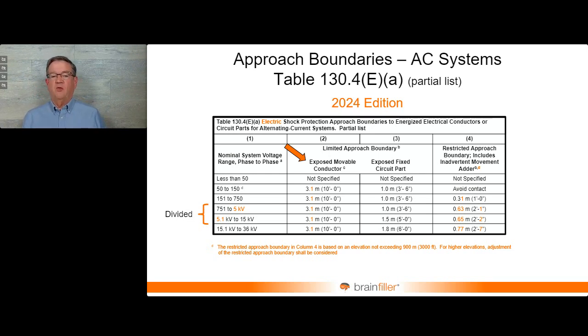Mathematically, it was rounded incorrectly doing this, but electrically, it's the way to go. 10 feet was something like 3.04 something meters. And so the 0.04, yeah, mathematically you round down, but that means that we're giving up that 0.04. That's a distance we really shouldn't be giving up. So the decision was made, well, let's round it up, so we still have that distance plus a little extra. And then for the restricted approach boundary, some of these numbers were changed to synchronize with the OSHA values. There was also a note added, and the note is about the restricted approach boundary may need to be modified based on elevations.